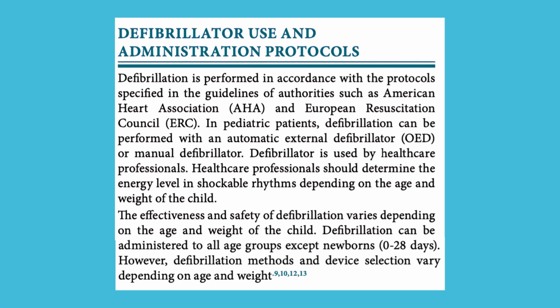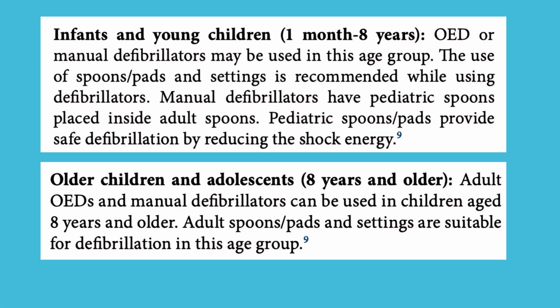Defibrillation can be administered to all age groups except newborns, 0 to 28 days. However, defibrillation methods and device selection vary depending on age and weight. Infants and young children, 1 month to 8 years: AED or manual defibrillators may be used in this age group. The use of spoons/pads in appropriate settings is recommended while using defibrillators. Manual defibrillators have pediatric spoons placed inside adult spoons. Pediatric spoons/pads provide safe defibrillation by reducing the shock energy.